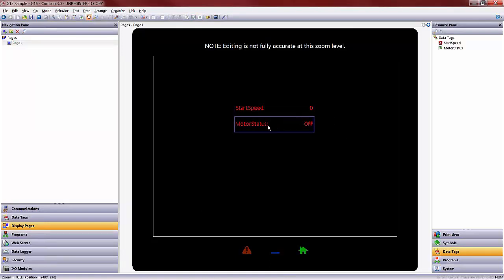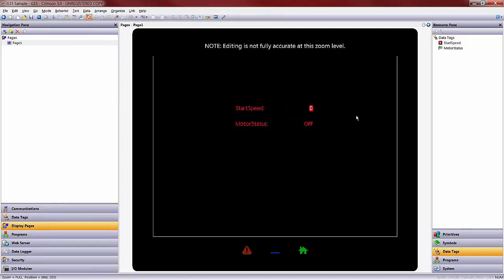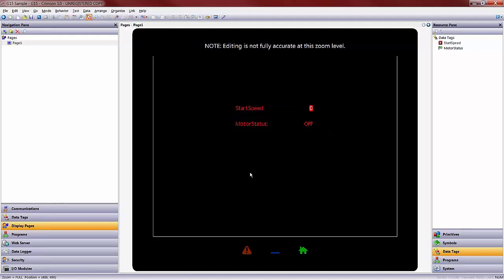From here, my motor status is a read-only, but my start speed is a read or write, so I could, in fact, open up, go to data, and create a data entry field as well, so that I could input a speed back to that percent R register in the GE controller. At this point, you have display and even feedback information back to a GE IP controller at the 192.168.1.2 address from our Red Lion device, G15, located at the 192.168.1.3 IP address.